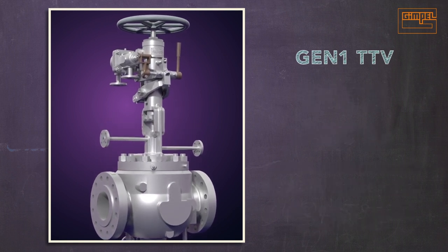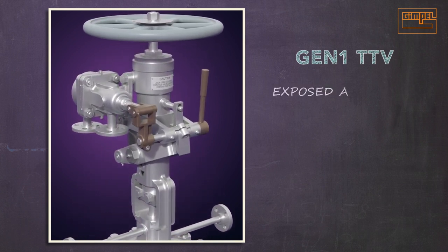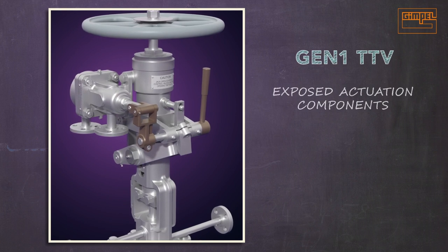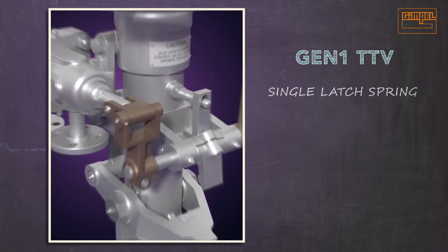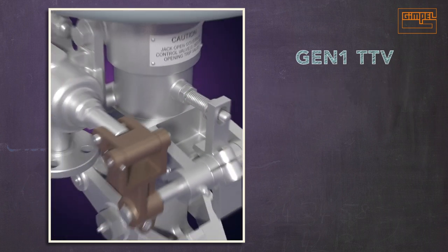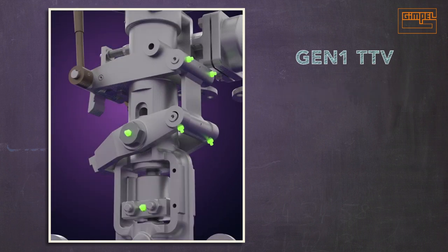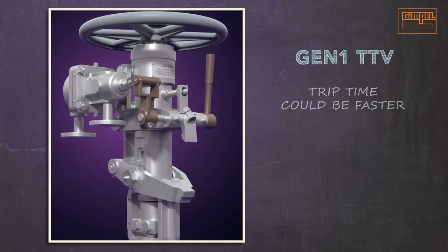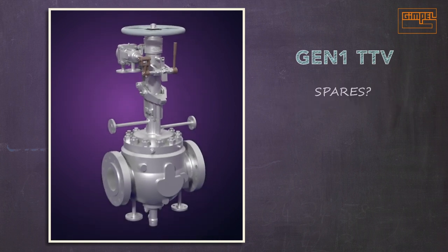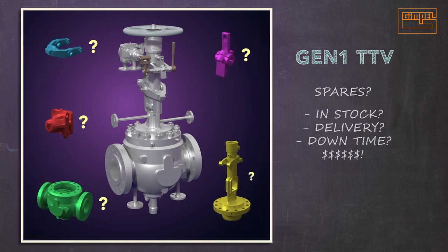Gimpel's design team looked at how the Gen 1 TTV could be improved. They identified actuation components that are exposed to the elements and create pinch points, a single latch spring with no redundancy, 9 lubrication points, a trip time that could be made faster, and most critically, the high cost and logistical problems of stocking and supplying spare parts — especially cast parts — needed for repairs and replacement for aging Gen 1 valves.